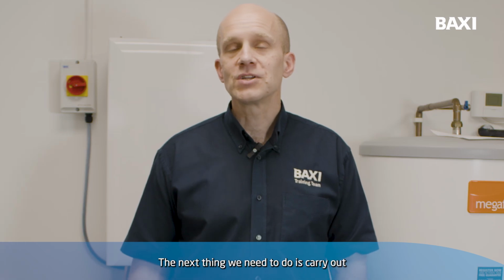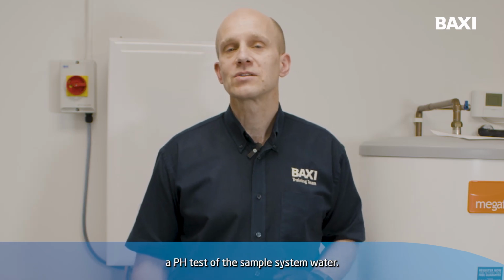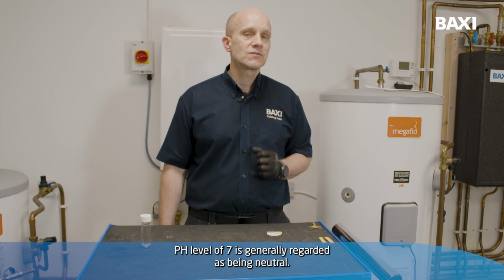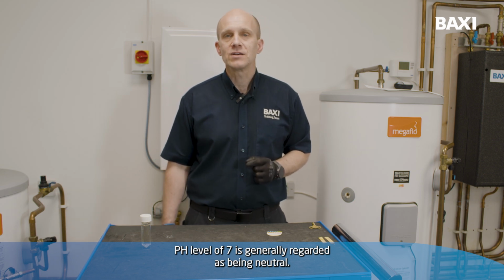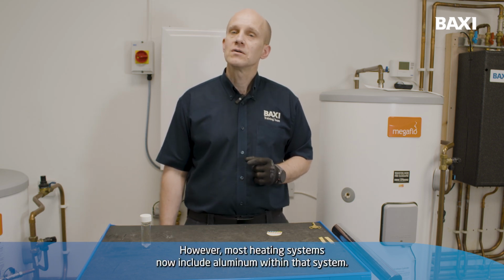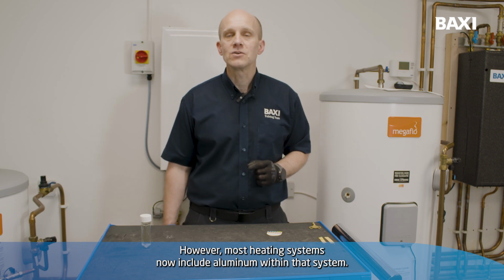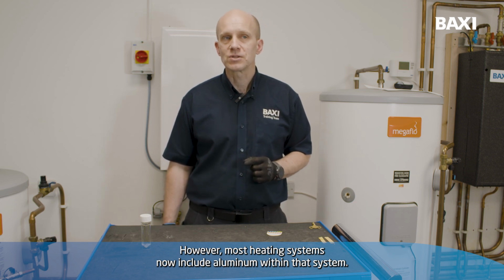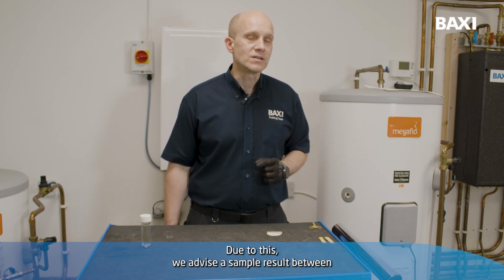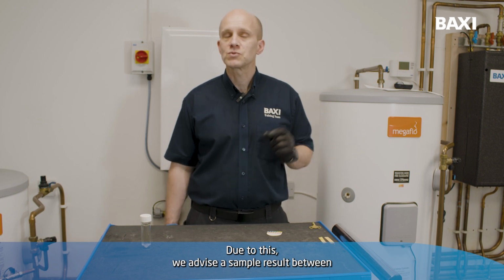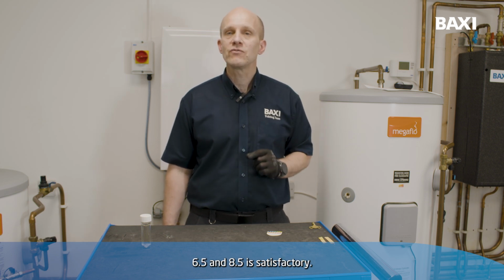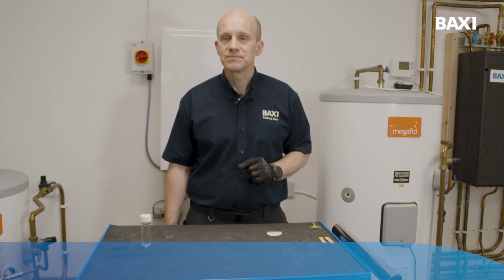The next thing we need to do is carry out a pH test of the sample system water. A pH level of 7 is generally regarded as being neutral. However, most heating systems now include aluminium within that system. Due to this, we advise a sample result between 6.5 and 8.5 is satisfactory.